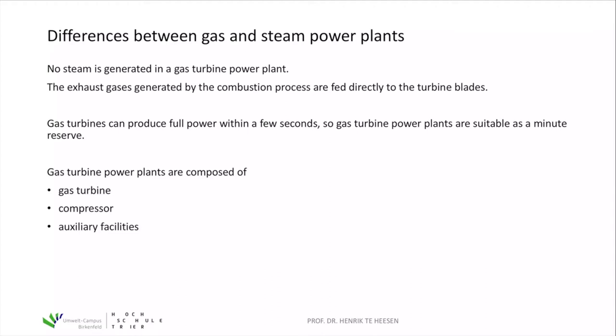The exhaust gases are generated by combustion processes and fed directly to the turbine blades, so they drive the turbine and the generator. One big advantage is that gas turbines can produce at full power within seconds — you just need to add the natural gas and burn it. Gas turbines can be available on the grid within seconds or a minute, and the concept is rather simple.